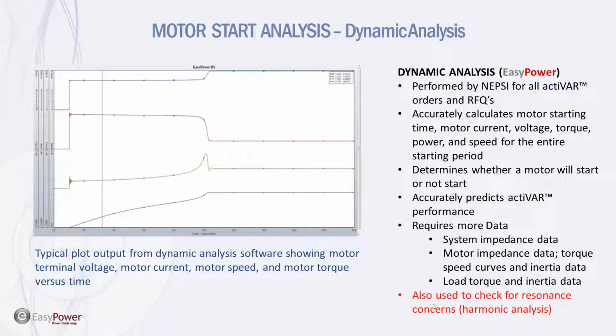And then we also do a starting analysis in which we're using the dynamic analysis package, and we're coming up with a before and after type of report where we look at and predict the voltage before the application of the actiVAR. In this case, we actually compare it to measurements that were taken on site during motor starting and compare that to our simulations to tweak our model and make sure it's correct. And then we apply the actiVAR to determine the performance and the required KVAR to meet the performance requirements for the project.